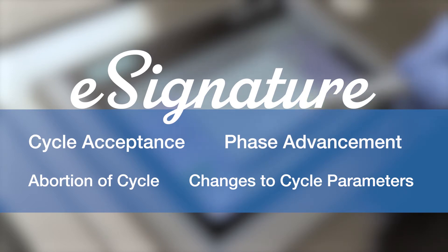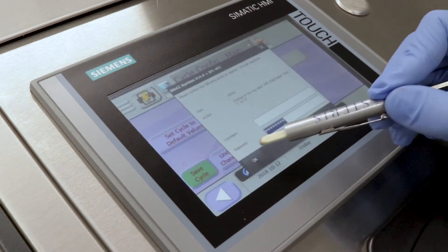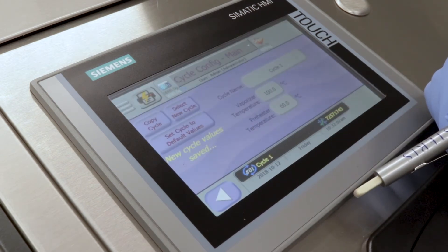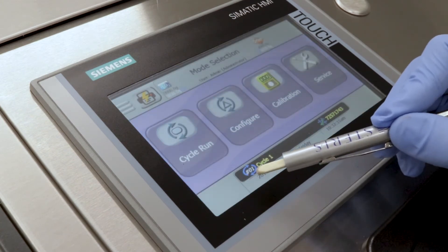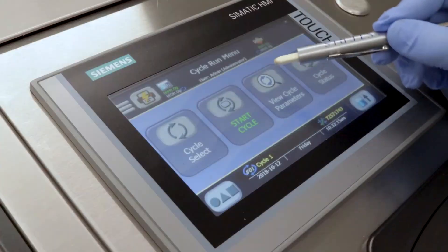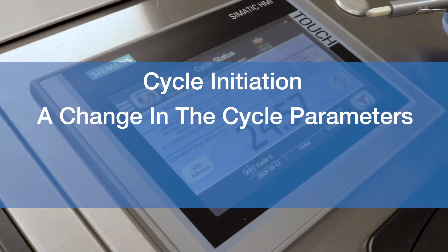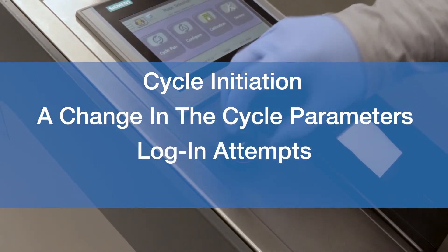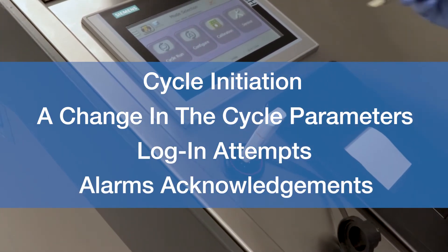Another important feature for 21 CFR Part 11 compliance is audit trail. The STERIS audit trail feature tracks users' actions through all critical functions as appropriate for the equipment type. All information captured in the audit trail is archived onto a memory card in the HMI in CSV file format. Actions such as cycle initiation, a change in the cycle parameters, login attempts, and alarm acknowledgements will be captured and can be easily retrieved from a desktop at any time.